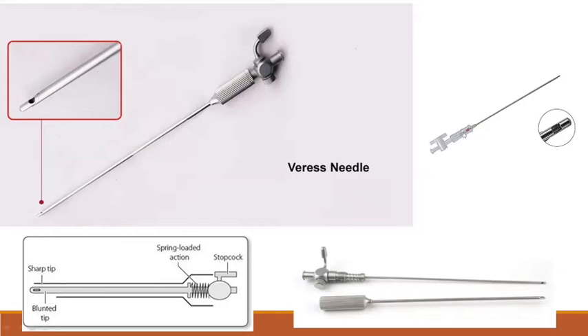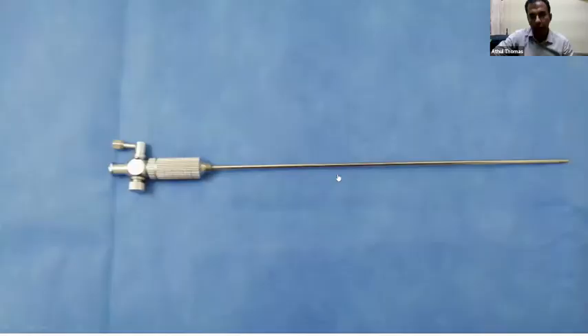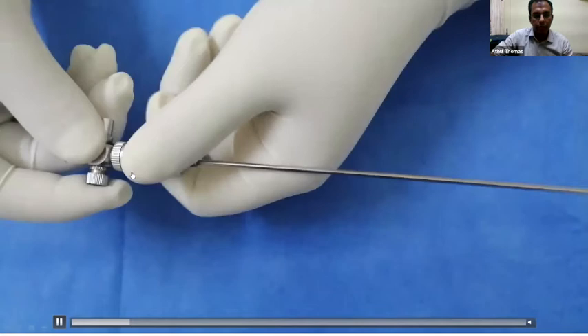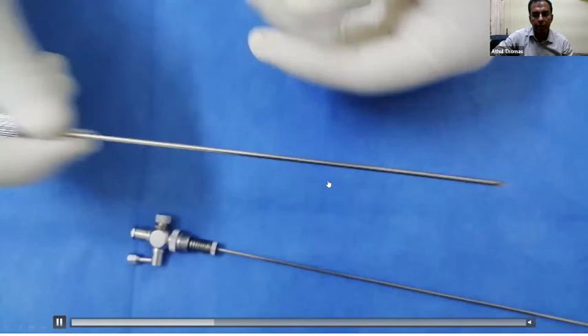The reusable Veress needle is shown here, and the disposable single-use one is shown without an inner stylet. We initially used the disposable ones but now use the reusable ones in our department. Our needle is around 20 centimeters, blunt at the tip, with a Luer lock. When opened, the inner stylet comes out revealing the sharp outer cannula, the blunt inner stylet, and the spring.